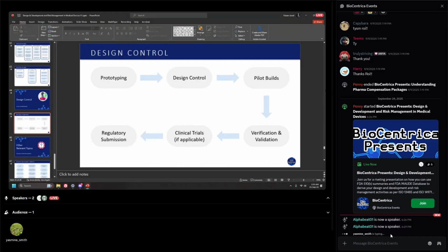So basically, if your final testing is getting passed, and it meets that performance testing standard that's mentioned in your particular medical device standard, then it's a good sign that your process is validated. But you still need that document to show it as evidence that you have validated your processes through these documents.